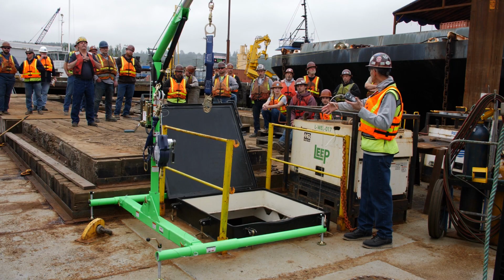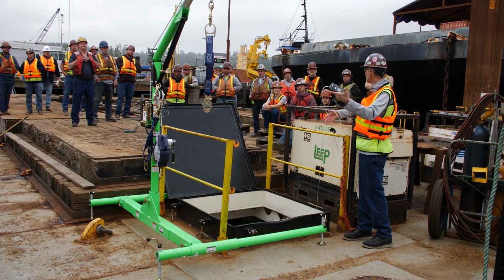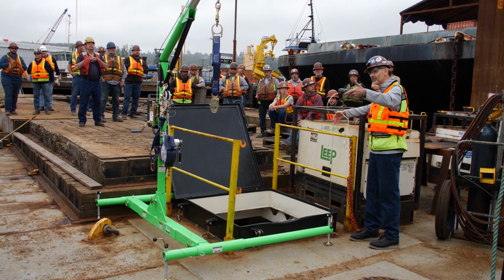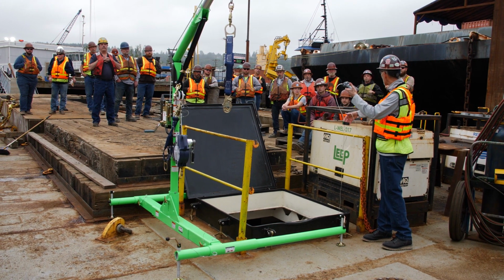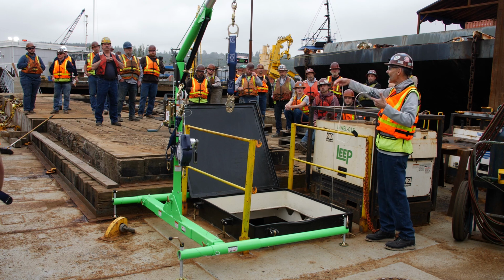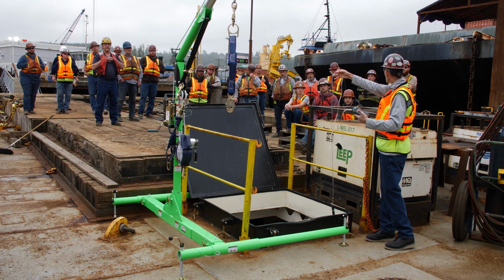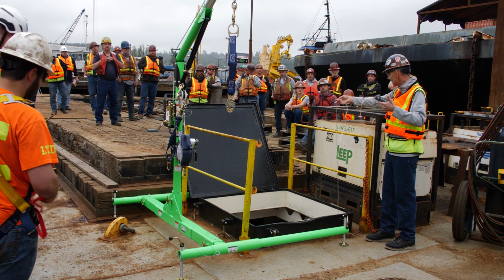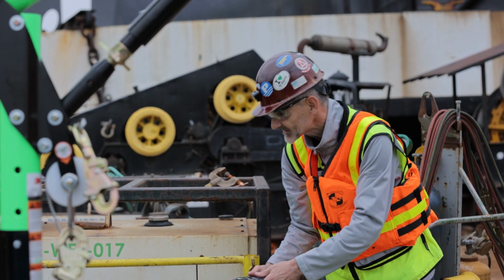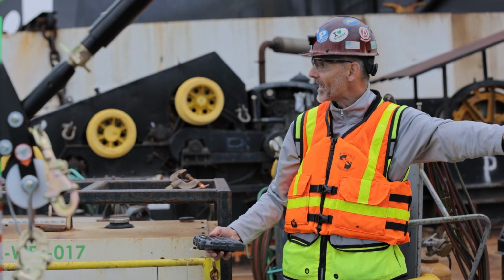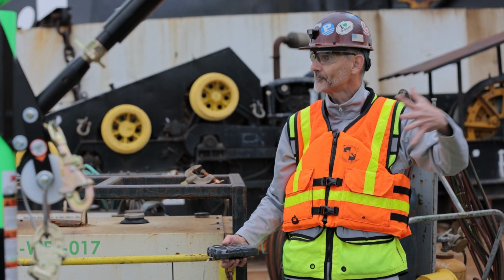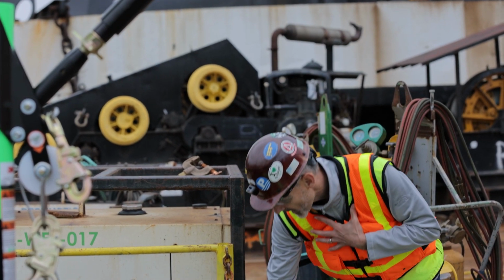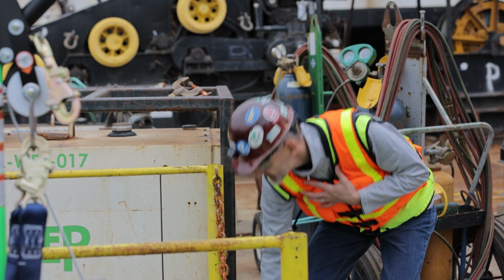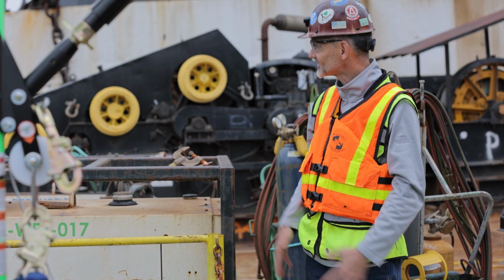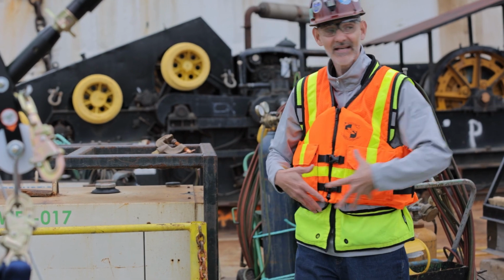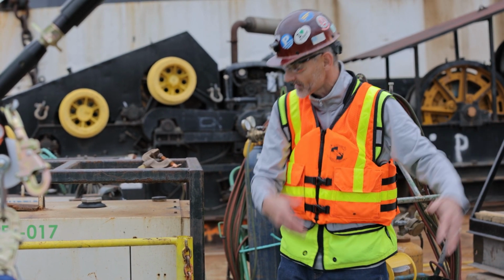Now, there's one of two things we can do when we put the worker into the space. If our worker is going to be working right down below, I can see him and I can run this sample line right near where he is working. I can leave this instrument topside with me. I'm the attendant. Here's our entrant. I'm watching him, which is required, that we have an attendant. I can set this right here in the space, watch it and listen for it as long as it's pulling a sample near where the worker is.